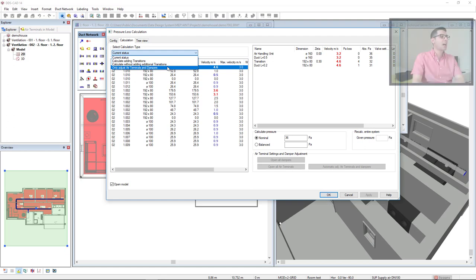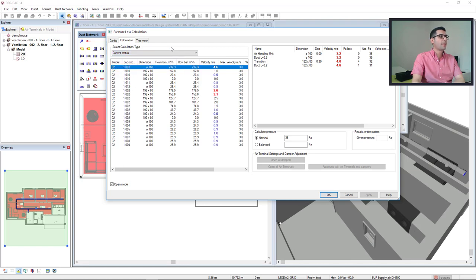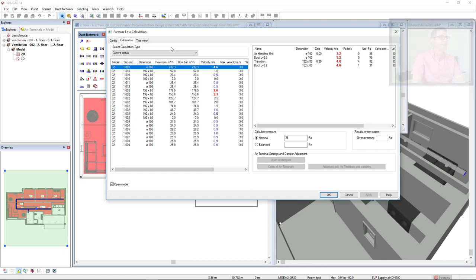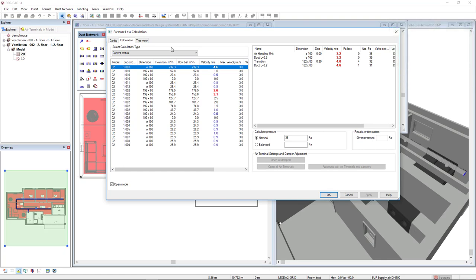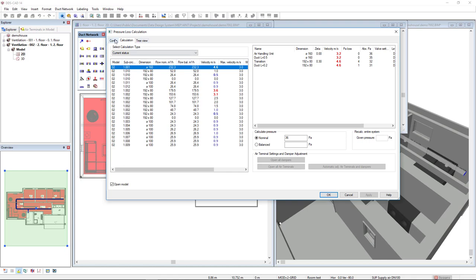In this case, I don't want to resize my model. I only want to show the results of the velocity in each duct segment. We see already in the preview that from the velocity limits that I have inserted as maximum of 3 meters per second and minimum 1, the values that are slightly under the minimum velocity. In red, we see the values that exceed the limit.